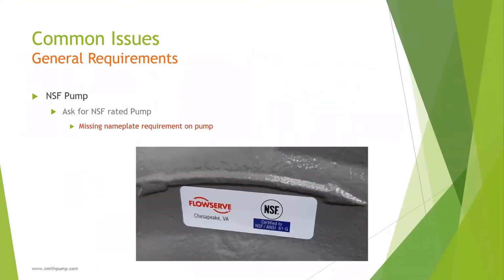When specifying an NSF pump for use in potable water, it needs to require proof, such as a nameplate on the equipment. The manufacturer should supply some sort of documentation at submittal time stating this particular product has been NSF 61 certified. The equipment should have an NSF nameplate on it as well. So meeting the intent of NSF or using NSF approved materials in lieu of the real NSF certificate should not be allowed. If materials are not certified by a third party, the owner has no proof of how safe the pump is for a public drinking water system.